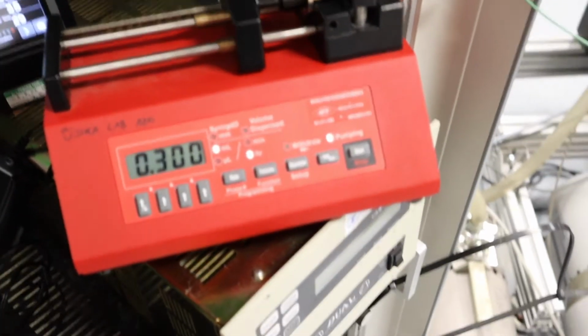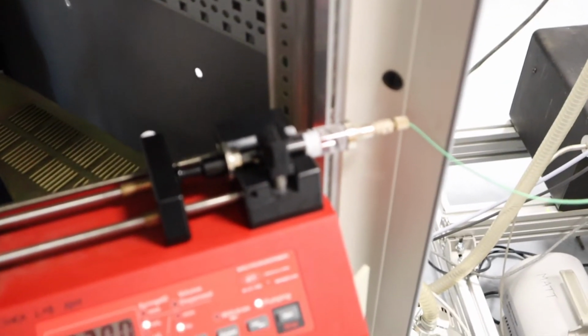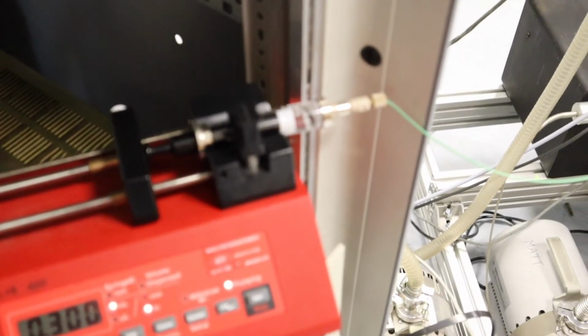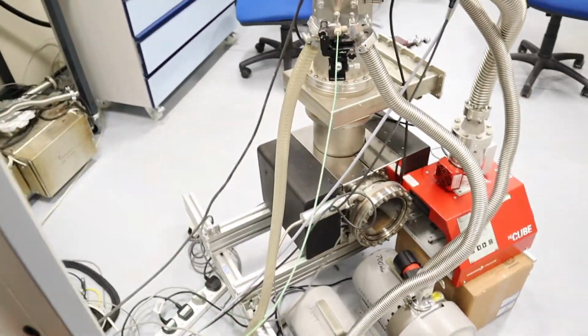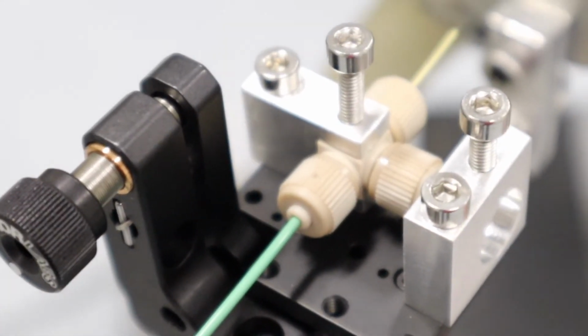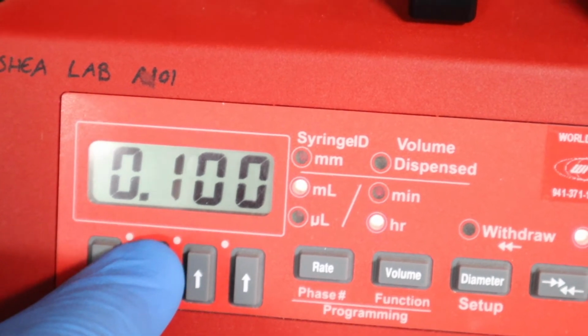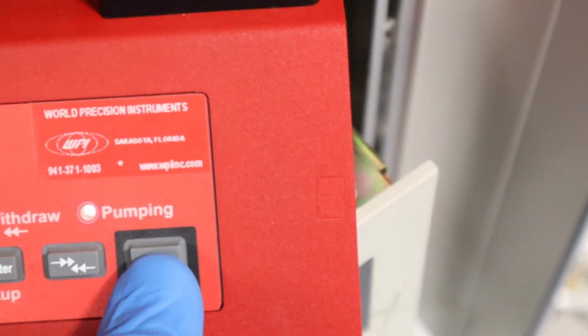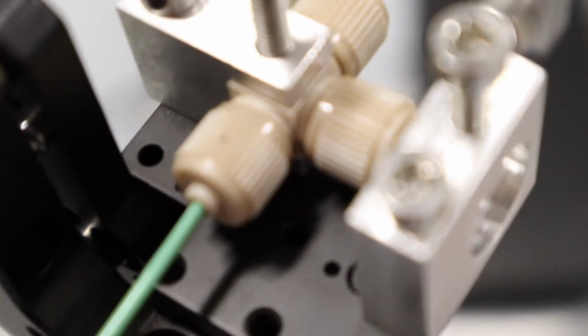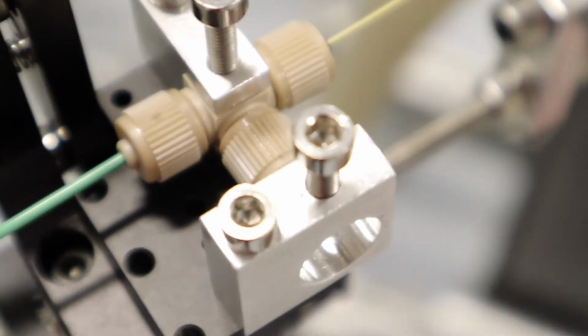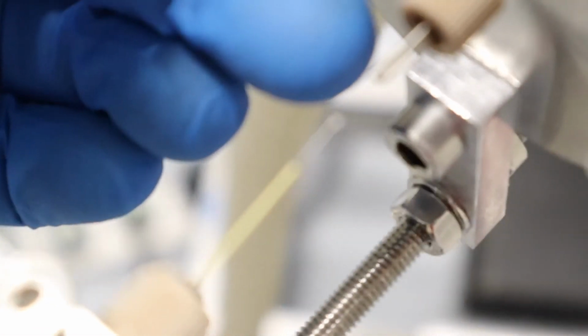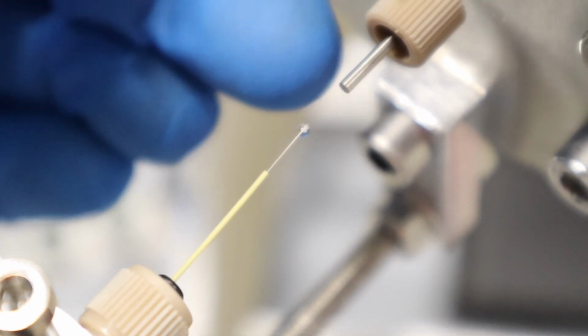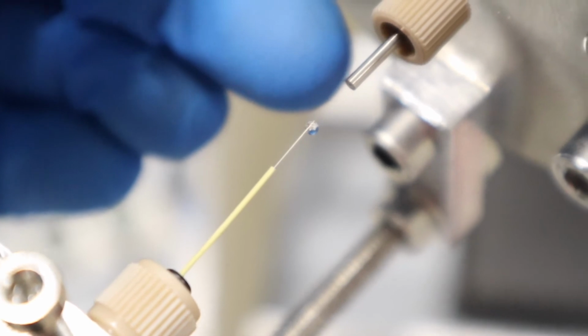I have a syringe pump here, and I have a 10 milliliter syringe full of methanol. Well, it's not full, and that's now attached to the electrospray T, and I'm going to set a flow rate of 0.1 milliliters per hour, and then I'm going to press the pump button to purge, which will send liquid down towards the emitter, and I'll just keep looking at the emitter to see if we get any liquid emerging, or if we get any liquid emerging from where we don't want it. On the end, if I focus there on the end, you'll see a droplet of liquid just emerging from the end of the emitter.